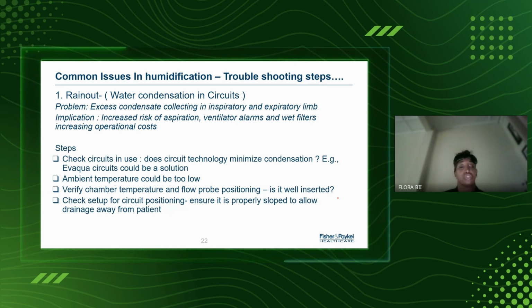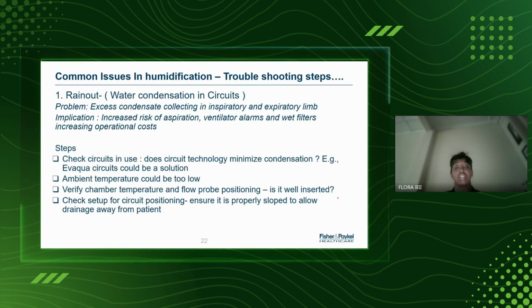The first thing to check, as a step you can take to troubleshoot this, is what you are using in terms of your circuits, because different circuits have different technologies that have been employed in them. Then the onus is on us to look at a circuit technology that would minimize condensation. Some circuits out there, like the ones called Evaqua, heat both the inspiratory and expiratory side, significantly minimizing condensation.